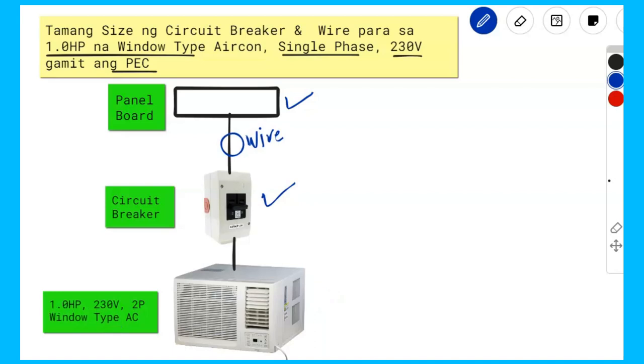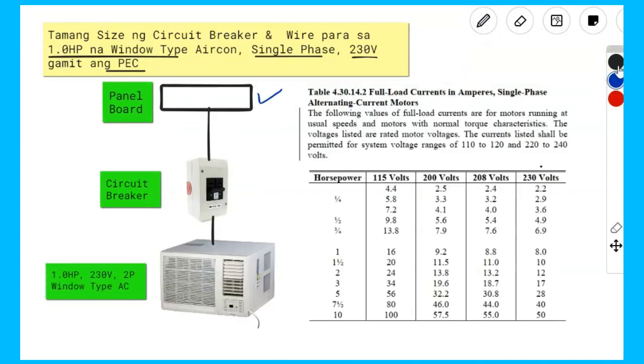Okay, so meron tayong table para sa pag-determine ng full load ampere ng 1 HP na aircon. So, tingnan natin. Ito ay galing sa Philippine Electrical Code, Table 4.30-14.2, the full load currents in amperes for single phase alternating current motors. Itong sa gilid, dito yung horsepower. And then, corresponding voltage: 115, 200, 208, at saka 230 volts.